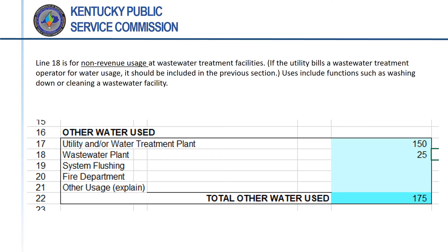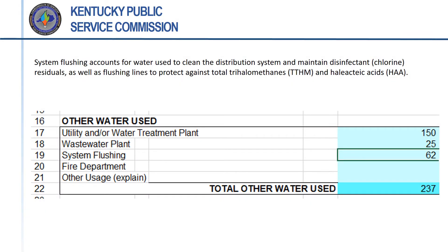If the utility charges a wastewater facility for any portion of its water usage or all water use, that quantity of water should be entered on the appropriate line in the previous section. Water used to flush a water utility system is entered on line 19. This is distinct from water used to flush portions of the water treatment plant. Water used to clean the distribution lines, maintain chlorine residuals, or reduce levels of trihalomethanes or haloacetic acids falls under this category of non-revenue usage.